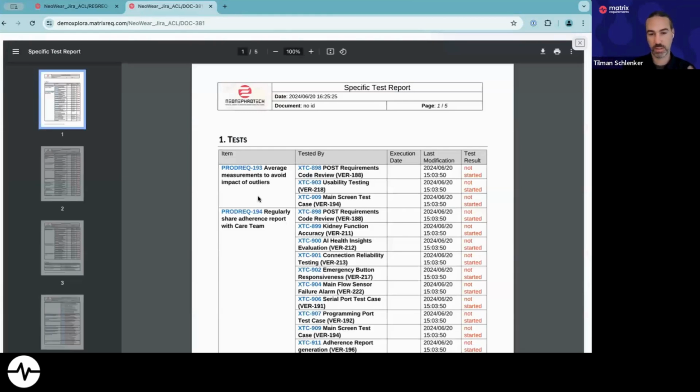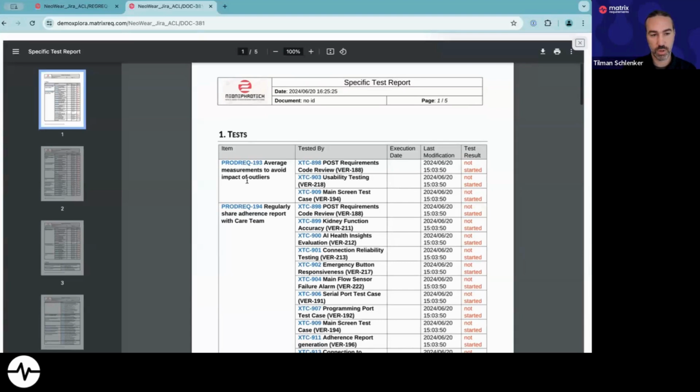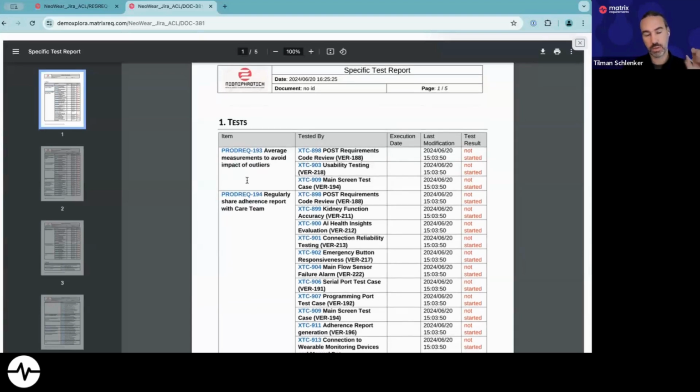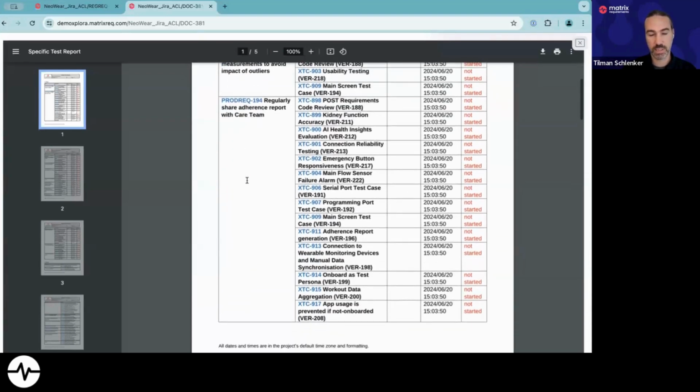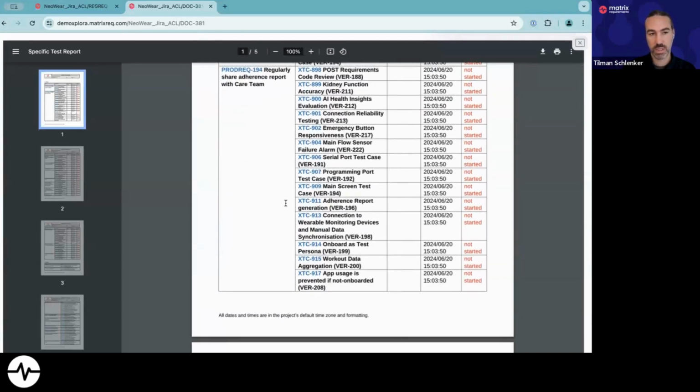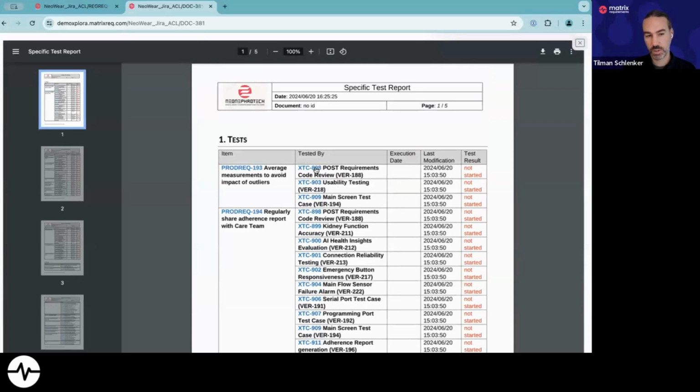And the complexity really depends on the criticality of your product. Is it class A, B, C, etc. The requirements will change based on this and the level of detail that you have to follow. But generally, I've just set up a new test plan for my testers or for my testing system. And what you can see here is that it traces down from, specifically in this case, all the product requirements that I identified that I want tested, down to test executions.